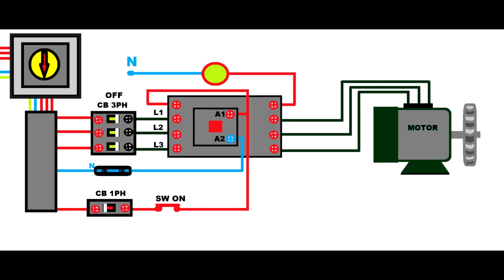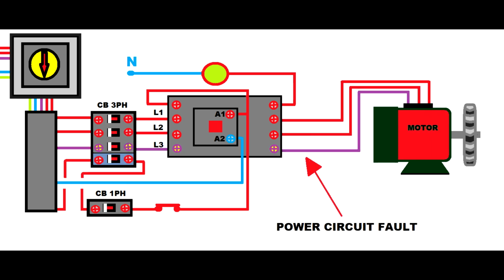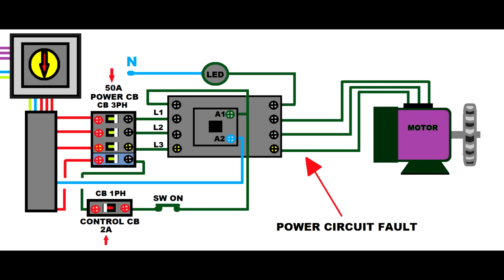If you remember, in the previous version, the control circuit is wired directly through the isolating switch, and it will remain on if the power circuit fails. Now if you choose this version, what you'll observe is that the control circuit is wired through the power circuit breaker, and if the power circuit breaker trips, it will interrupt the power to the control circuit. So the control circuit will be inactive as long as the power circuit breaker is tripped. You can follow this diagram.